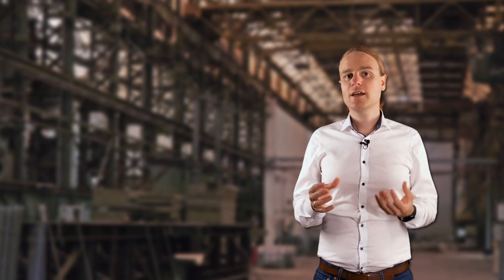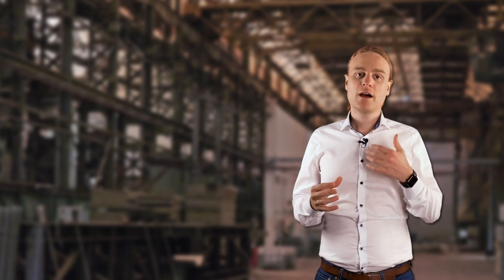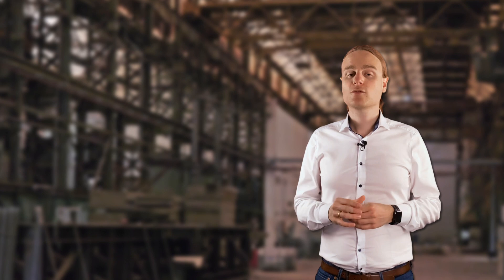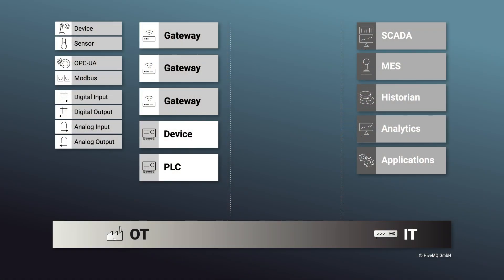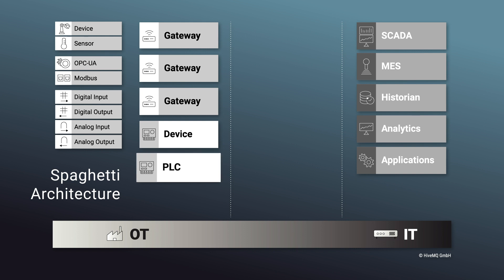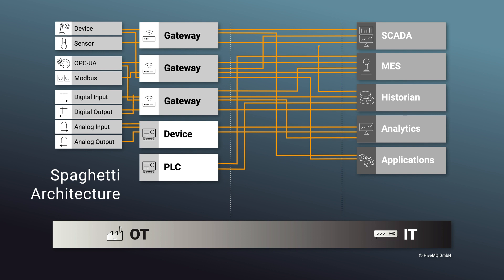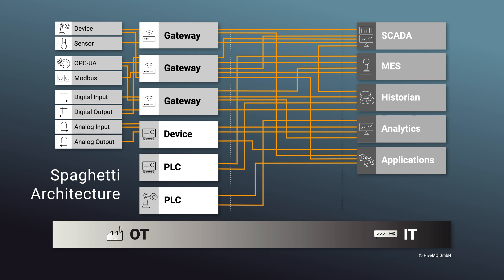Before we go into the Sparkplug architecture, let's take a look at a very traditional, probably OPC UA based or other protocol based architecture, which you will find today in a lot of factories and shop floors. As you can see in this picture, we have what we call a spaghetti architecture. A lot of the components — PLCs, gateways, machines, applications, SCADA systems, historians — are usually connected point to point. If you're adding a new PLC to your deployment, you need to make a point-to-point connection to your respective systems, resulting in something very hard to maintain. This is because a lot of these deployments use a so-called poll-response architecture, which we will also talk about in detail in later parts of this series.